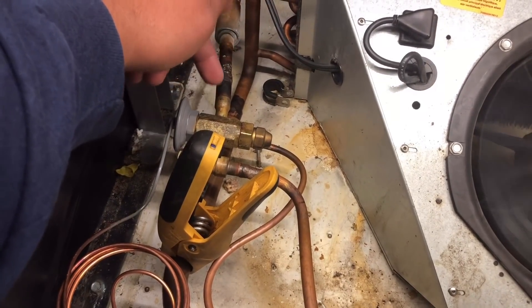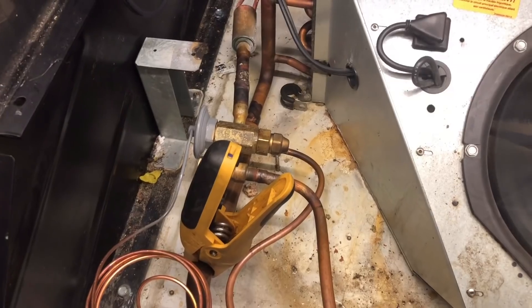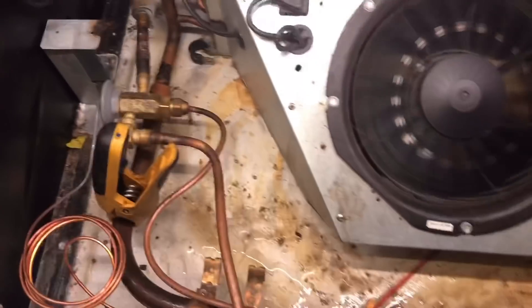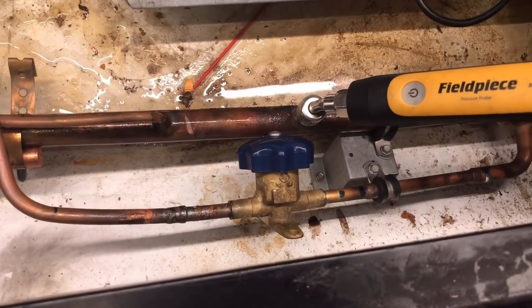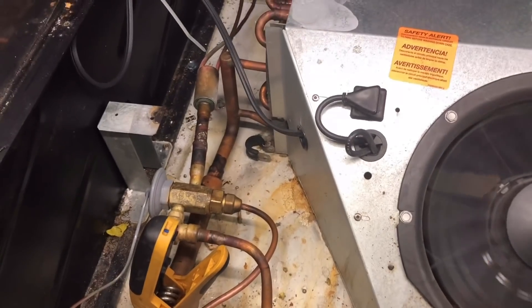What we're gonna do is I have the EPR overridden to about 37%, which from past experience seems to be the magic number. I have the hand valve closed right now, but I'm gonna open it up and check my saturated suction temperature. As long as we can maintain about 20 to 22 degrees we should be good. The EPR opening up too much makes our valve appear a lot smaller than it is, showing 44 degrees superheat when in reality it's not starving.